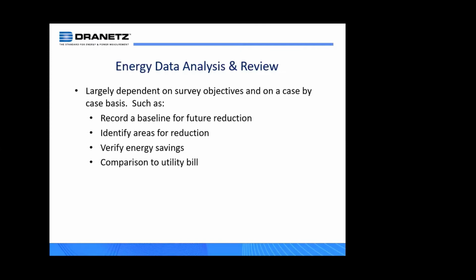And now we even add another bullet here. We've seen scenarios where they're verifying the accuracy of an existing meter, an existing revenue meter. We've seen many cases in which the revenue meter has been off. And with the revenue meter being off, then obviously your bill is incorrect. So there's a number of different scenarios that you would encounter here for energy data analysis and review.